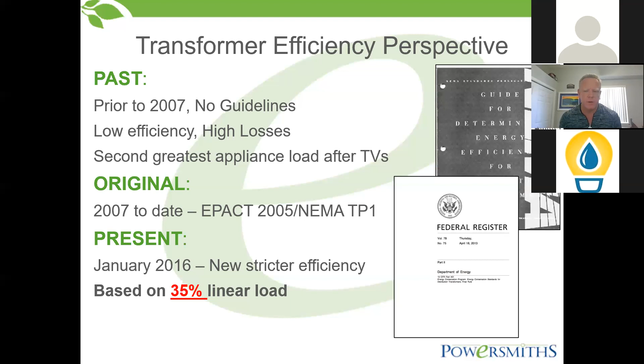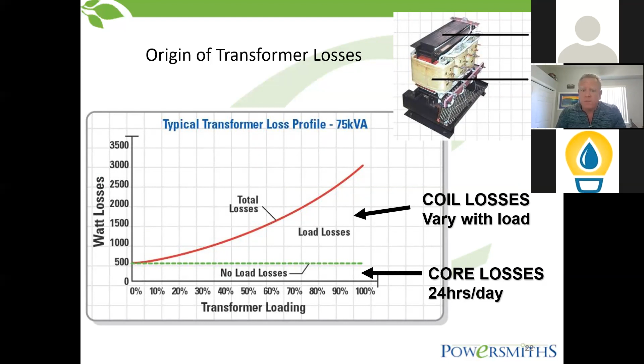The majority of the losses in a transformer are the core losses. Those are the losses that are 7x24, 365. You turn on a transformer, go home at night, turn off all the lights, turn off all the computers, that transformer is still on. There's core losses in that transformer 7x24, 365. And then there's coil losses varying with load.